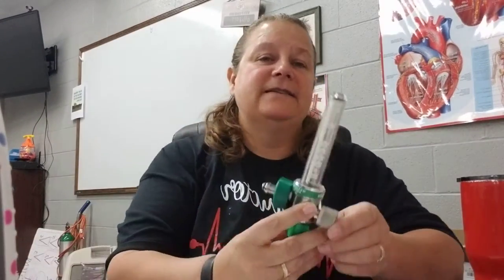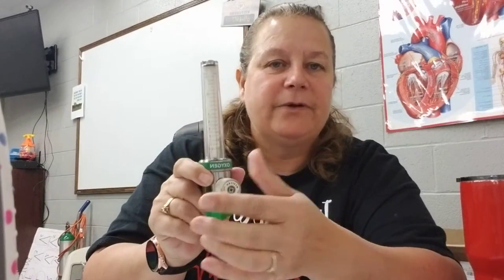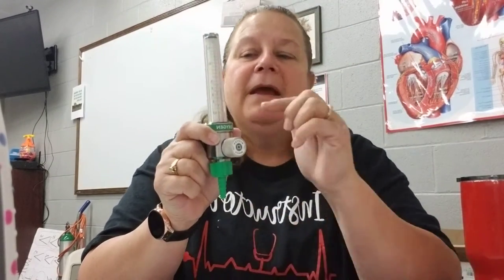It's important that you are familiar with your facility's equipment. This is an oxygen unit that you would see in a hospital — it goes into the wall, which is connected to the oxygen supply and the oxygen tank. It has two main hooks, and you move this to change the flow of the oxygen. It also has a ball — the level of the oxygen is where that ball floats.